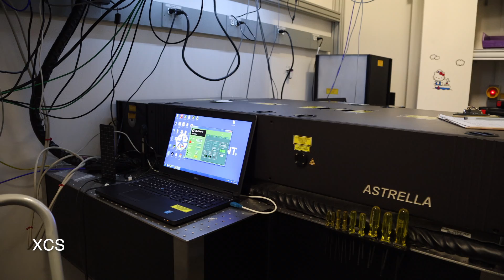The laser can be frequency converted via harmonic generation or optical parametric amplification to generate wavelengths in the range of 260 to 2600 nanometers. The laser focal spot is typically 50 to 100 microns full width at half maximum at the interaction point, and the available pulse energy is strongly wavelength dependent. Motorized control of the laser pulse energy and polarization are also available. Discussions with the laser and instrument teams are strongly encouraged before proposal submission, especially for non-standard laser delivery requirements.